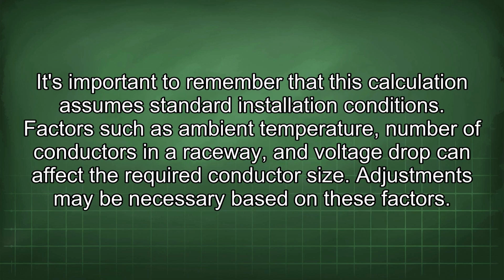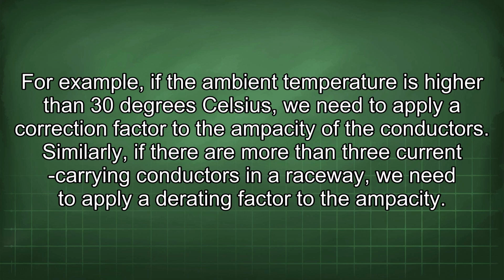It's important to remember that this calculation assumes standard installation conditions. Factors such as ambient temperature, number of conductors in a raceway, and voltage drop can affect the required conductor size. Adjustments may be necessary based on these factors. For example, if the ambient temperature is higher than 30 degrees Celsius, we need to apply a correction factor to the ampacity of the conductors.